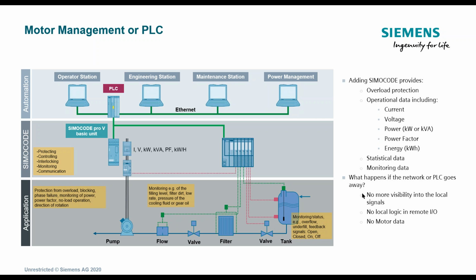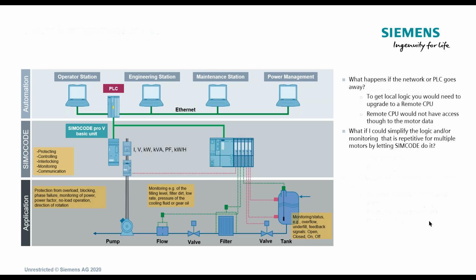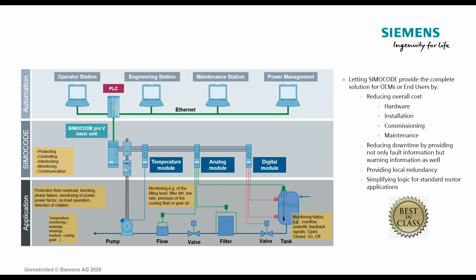Okay, we introduce the SIMOCODE, and now we have that. And we pull in the SIMOCODE. We have the temperature module for maybe the bearings on the pump. We have an analog coming in. We have a filter with a delta P, pressure differential. Then we have some digital inputs of the valve opening and closing, and then we have some tank level sensors. And everything is pulled into the SIMOCODE with local logic in the SIMOCODE reporting back to the controller. So now we do have the monitoring that we need to have.